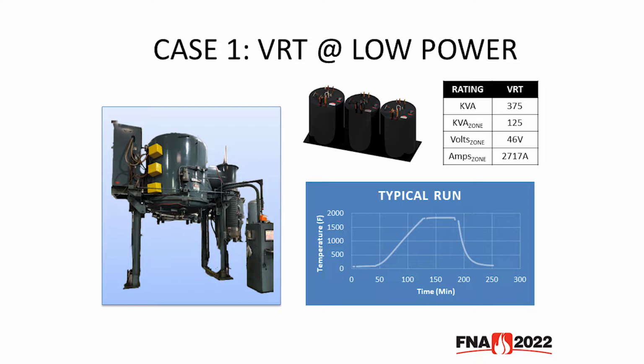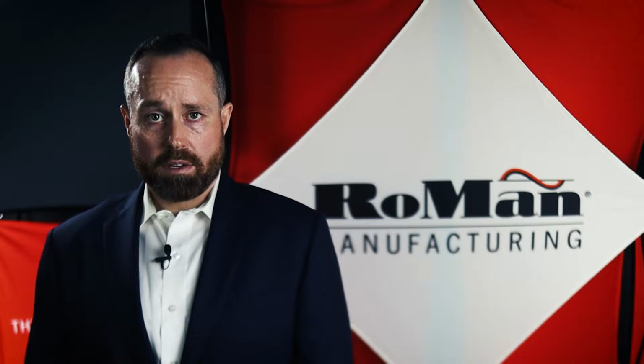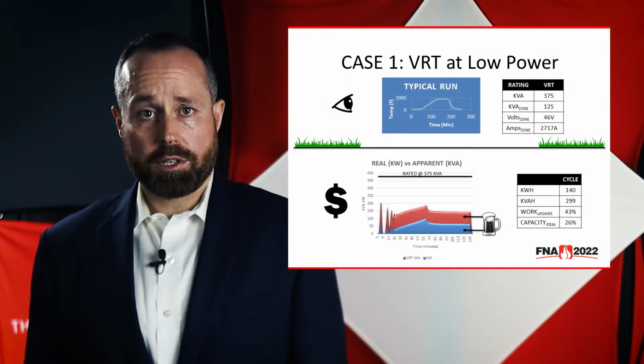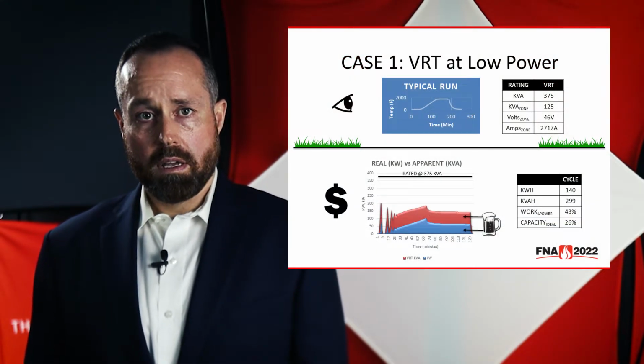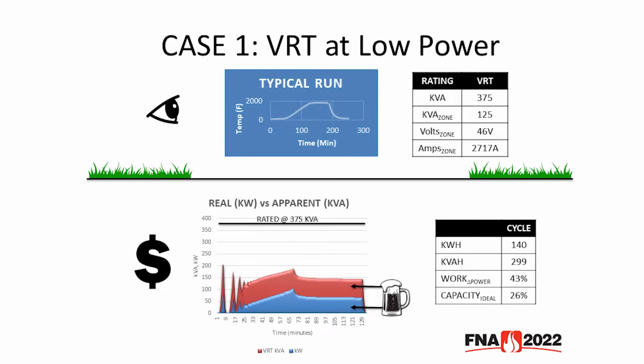A typical run was performed, and the power quality was assessed in only the heating circuit. The cycle shown here consists of a ramp up to and hold at 1800 degrees Fahrenheit. The run was completed without any issues. On the surface, everything looks fine. That is until we examine the electrical characteristics of the furnace. The graph below shows a total power consumption of the furnace for this cycle.